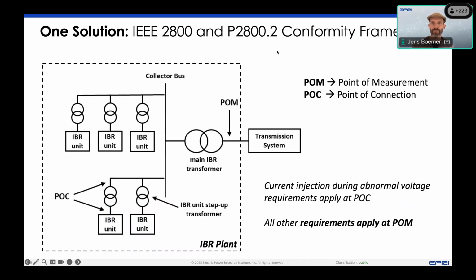As a quick reminder, most of the requirements of IEEE 2800 apply at the point of measurement, usually the high side of the main IBR transformer. There are a few that apply at the unit level. That's the reason why modeling is certainly the best practice to account for all the ins and outs of how the equipment is designed and how the controls are designed, which determines the plant's performance at the POM. But there might be good reasons why we don't always want to model everything, so that's the idea of today's presentation: to look at what else we can do instead of only modeling.